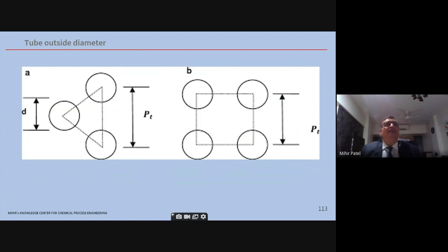Then the tube outside diameter, as you can see, the D is the tube outside diameter and PT is the pitch. So the normal tube ODs are 15.88 mm, 19.04 mm, which is 3/4 inch, and 25.4 mm. Smaller tubes give more turbulence, but then cleanability is an issue. Larger tubes are used in critical services like a sulfur condenser in an SRU.